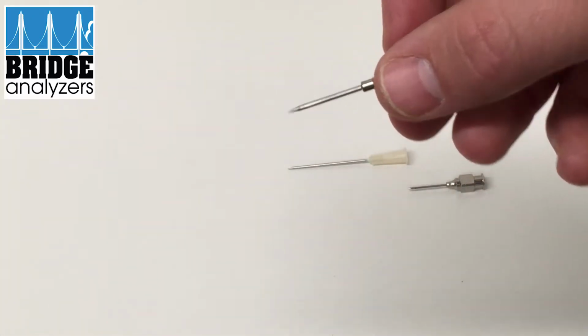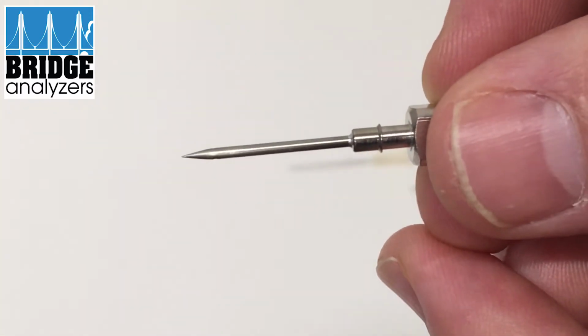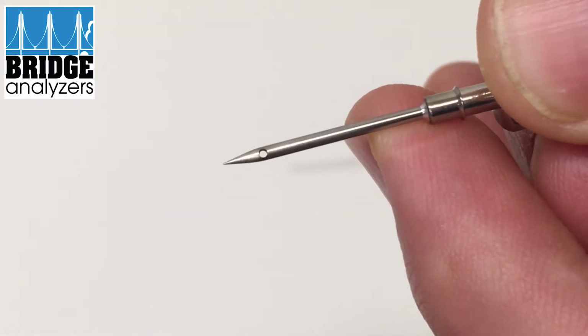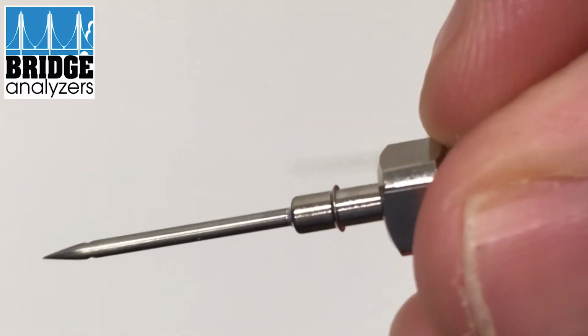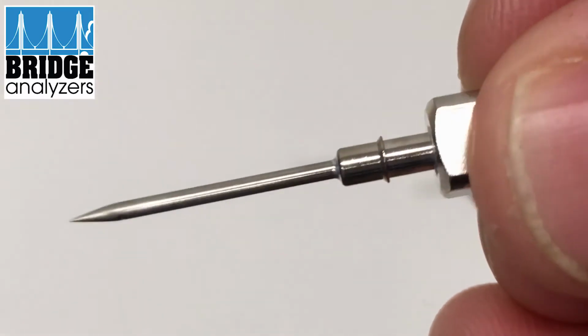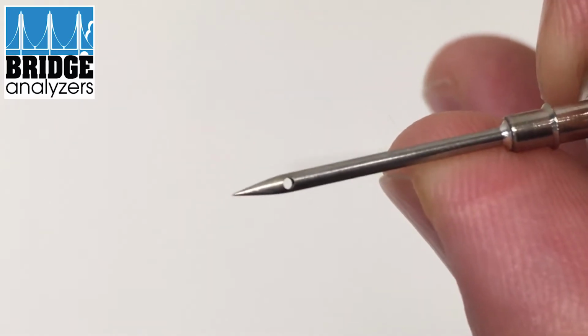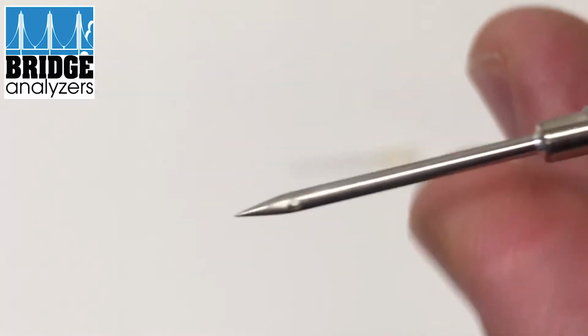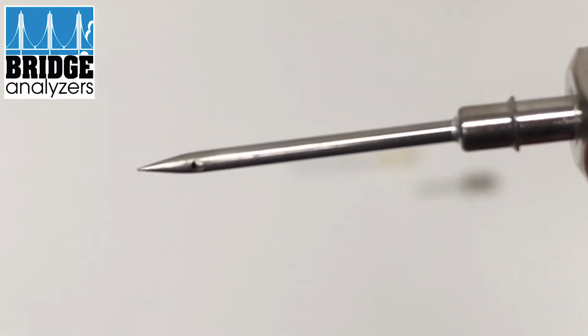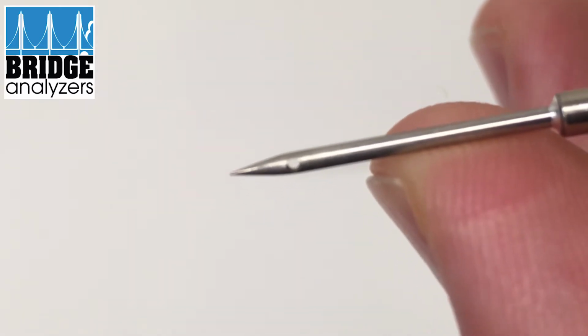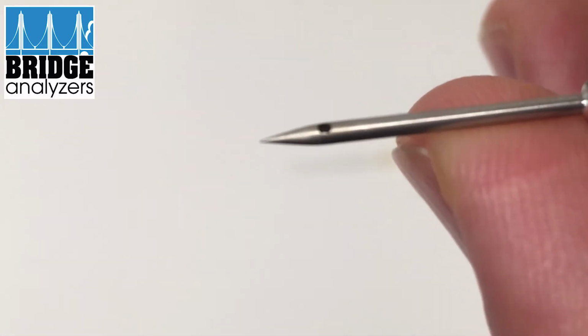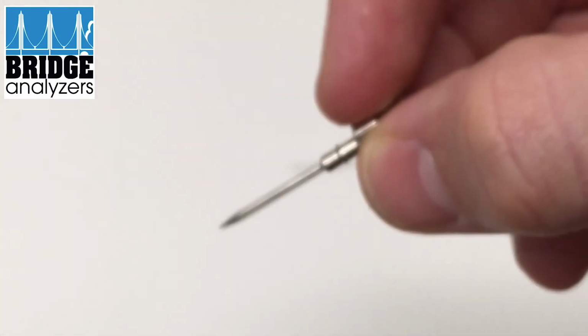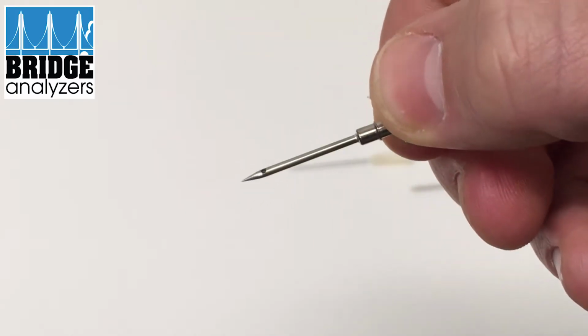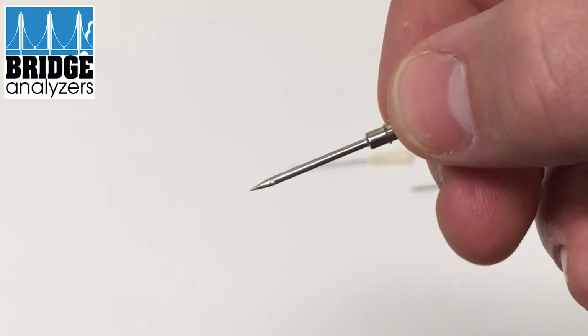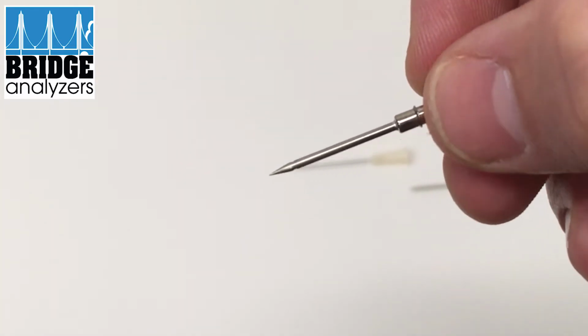We have a second one as well, which we designed for customers that want a thicker gauge or a larger gauge needle. And also it has a barbed fitting at the end, which is used when they do calibration gas testing. But you'll see the same cross-drilled hole here. You can see it better because it's a thicker gauge. And this was designed mainly for the case-ready meat market. And so what they do when they do their testing is when they're finished testing a package, they will cut the film wide open because they're going to repack that meat. And what we were finding was that with our standard needle, those needles were bending because they used the needle to actually cut the film. So we went to a thicker gauge, and it's been very successful in that market.